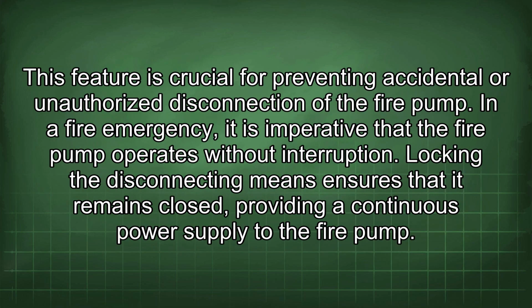This feature is crucial for preventing accidental or unauthorized disconnection of the fire pump. In a fire emergency, it is imperative that the fire pump operates without interruption. Locking the disconnecting means ensures that it remains closed, providing a continuous power supply to the fire pump.